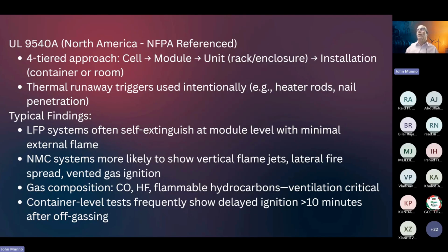And the typical findings are that lithium iron phosphate systems often self-extinguish at the module level with little external flame, whereas nickel, manganese, cobalt systems are more likely to show vertical flame jets and lateral fire spread, or vented gas ignition. The gas that comes out is carbon monoxide, hydrogen fluoride, and these are flammable. A lot of people don't think of carbon monoxide as a flammable or combustible gas, but in the right concentrations, it certainly is. And ventilation is critical so that we don't build up an explosive concentration, or we can use the sparkers like Tesla does.